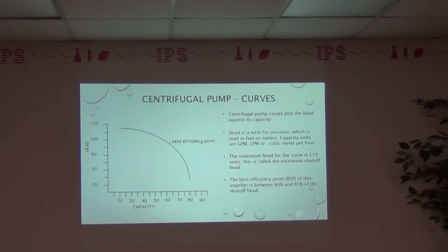So I take that, and then on the discharge end, I do the same thing. Based on what my flow is, my run of pipe, I'll take out my friction losses, elbows, valves, and so on and so forth. And then anytime I go vertical, it's a direct impact to my pressure. So I take those calculations together. Take my known energy on the suction side that will allow the fluid to freely move, subtract my known obstructions of flow on the discharge, and when I put them together, I can work out what my actual discharge or head pressure is required.